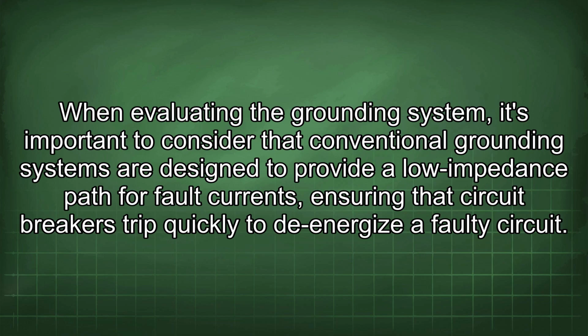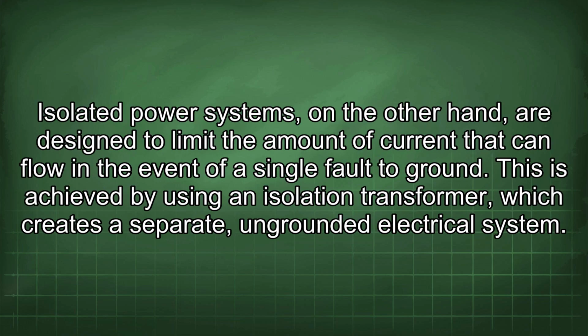When evaluating the grounding system, it's important to consider that conventional grounding systems are designed to provide a low impedance path for fault currents, ensuring that circuit breakers trip quickly on a faulty circuit. Isolated power systems, on the other hand, are designed to limit the amount of current that can flow in the event of a single fault to ground.